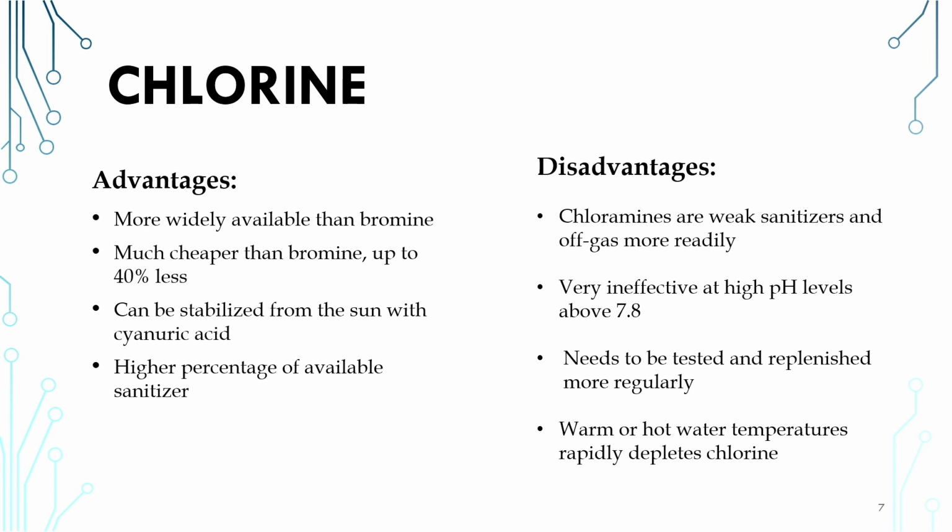Some of the disadvantages, however, are that chloramines are weak sanitizers and off-gas more readily. They're very ineffective at pH higher than 7.8. They need to be tested and replenished more regularly, and warm or hot water temperatures rapidly deplete chlorine.